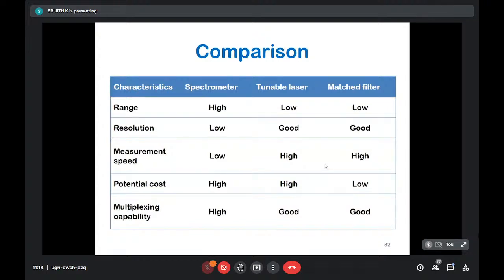In terms of resolution, it is the tunable laser and the matched filter that have better resolution than the spectrometer, as well as better speed. You cannot use a spectrometer for dynamic measurements. Dynamic as in something which is changing very fast, something like kilohertz or hundreds of kilohertz. You cannot use a spectrometer. That is when you have to go for these other interrogation techniques.